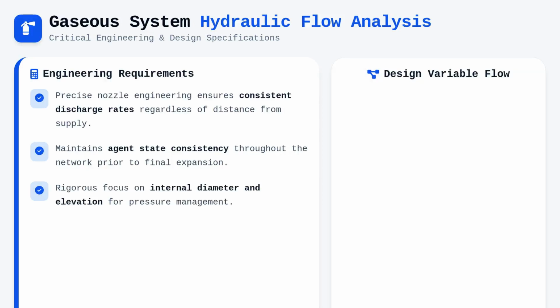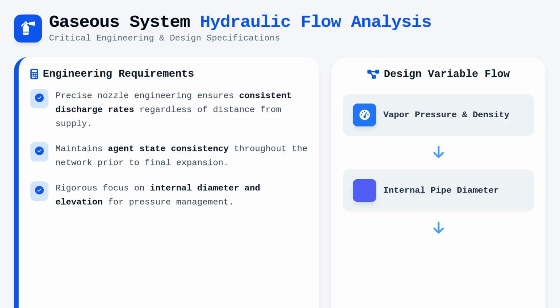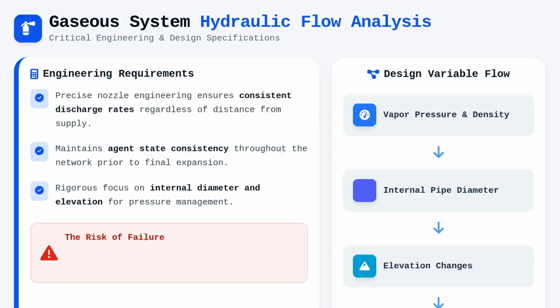Unlike water-based systems, these gaseous systems rely on the specific density and vapor pressure of the agent, making the piping internal diameter and elevation changes vital variables. Designers must strictly adhere to NFPA 2001, ensuring that the piping integrity supports high-pressure discharge. Failure to account for the specific agent properties will lead to improper mixing within the room, leaving pockets of unsuppressed hazards that could permit fire growth despite the system activation.